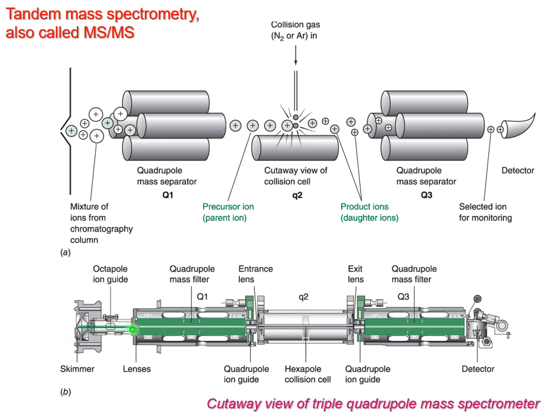Ions are coming in—mass filter, collision cell or collision chamber, and then the second mass filter. Selectivity of such instrument is fantastic. You are selecting only one type of ion, but of course it can be a coincidence—it can be several different ions having exactly the same mass. Then you run collision. Probability that these ions with exactly the same mass but different structure will produce exactly the same product ions is very low, so you have doubled selectivity of your determination. It's a very powerful machine and it's widely used in difficult toxicology problems.